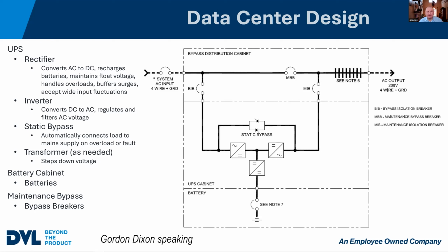But a lot of applications are using it. So you've got the transformer inside the UPS and you step down the power as you need it. So again, it's going to depend on the particular application, but that's the last primary component inside the UPS itself. Now, with regards to a UPS system, 3 primary components of the UPS I just talked about, and then you're going to have battery cabinets. Battery cabinets are going to be a big part of the first cost of the UPS, also the maintenance of the UPS.